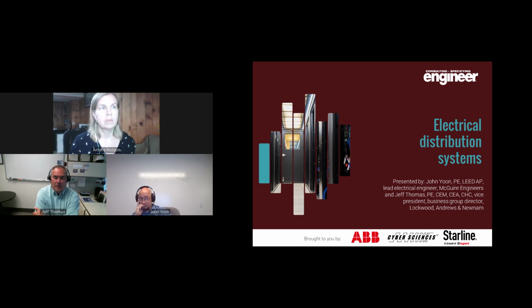Sure. So obviously, voltage drop is clearly a function of the current we're going to try and run down the wire, and it really becomes a cost discussion as much as anything else. If we're going to run a lot of current a long distance, we're going to pay for a lot of copper. We have a cost associated with that versus taking up another 100 or 200 square feet in a building. And that's a negotiation that has to happen with the architect. Ideally, our electrical room would be right smack in the center of the building, so all of our runs would be as short as possible. But we know that's not realistic. So we try and compromise. If there's an elevator core, maybe we can get near there and just go vertical in the building. So it's really just a return on investment kind of discussion based on what the building is going to be used for and how much space the architect can give us.